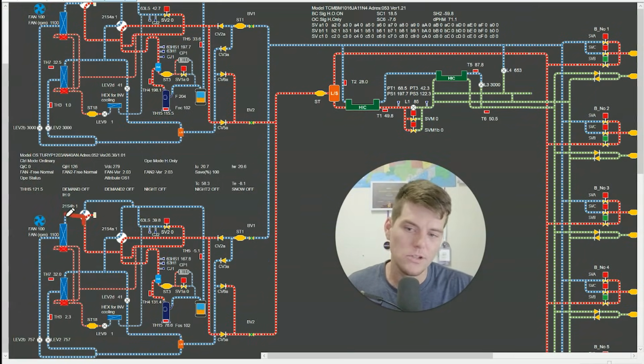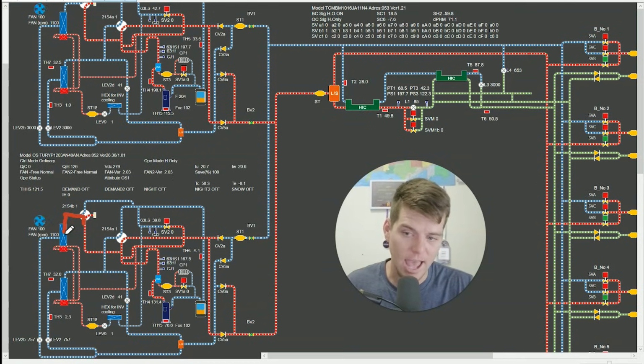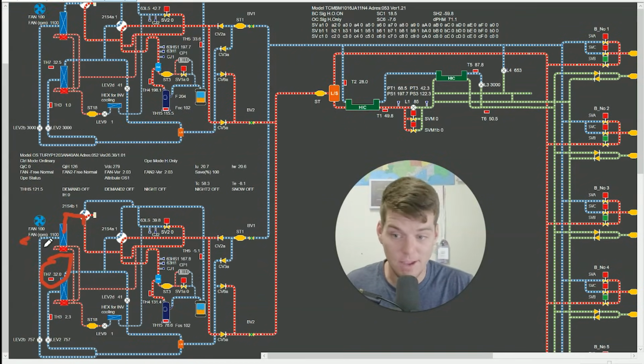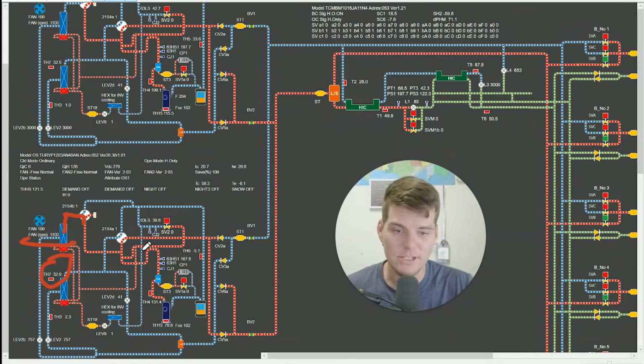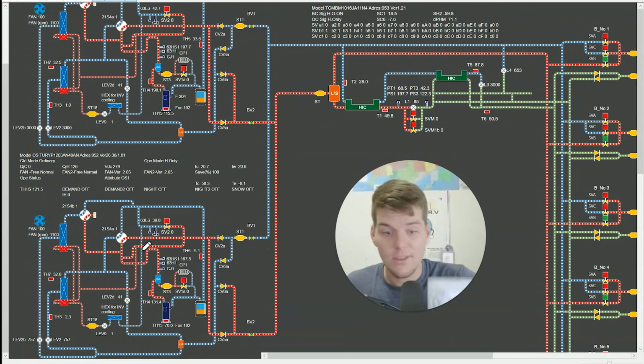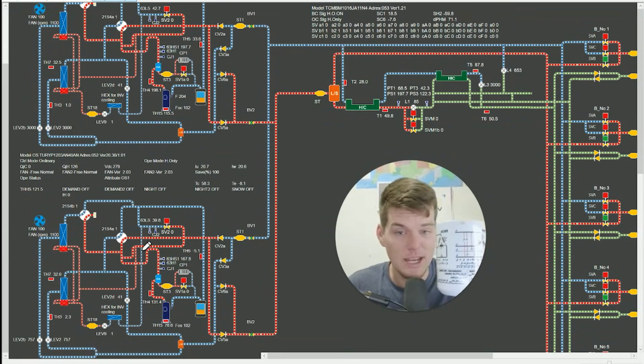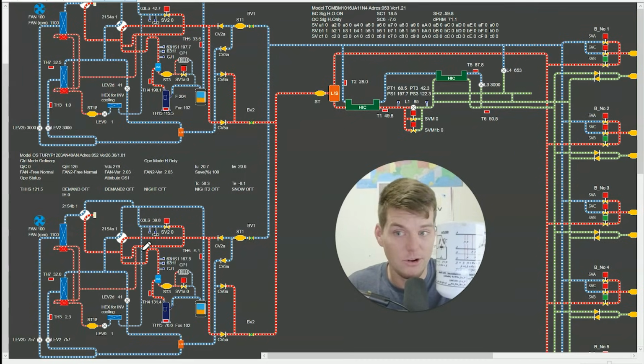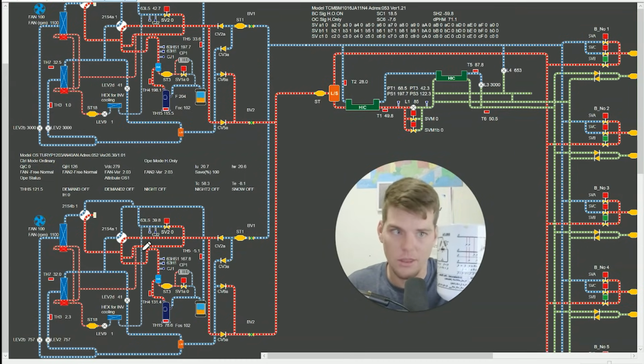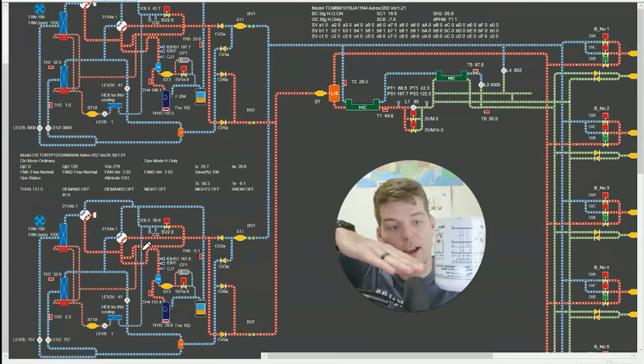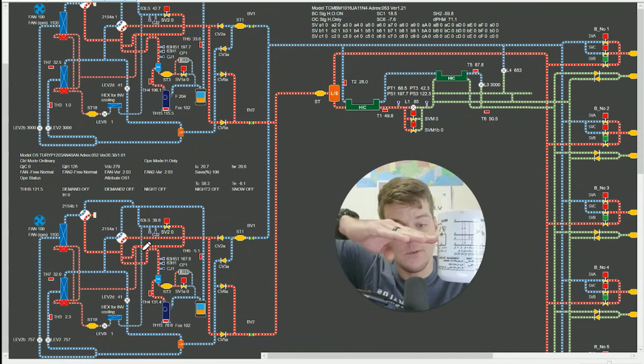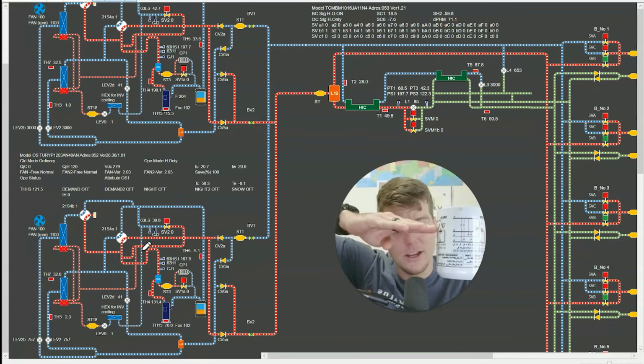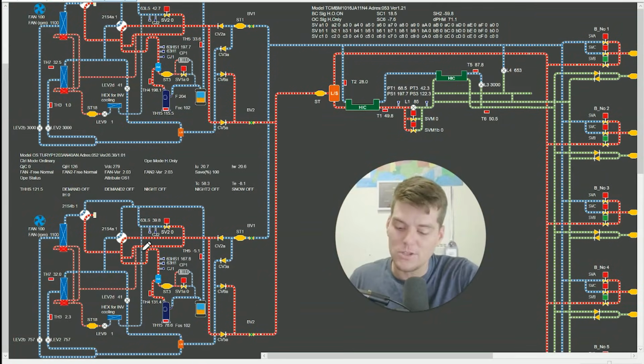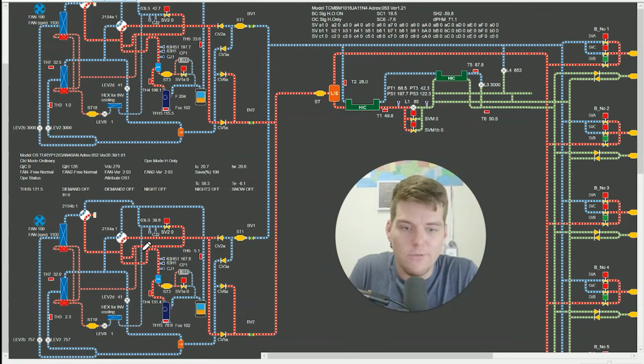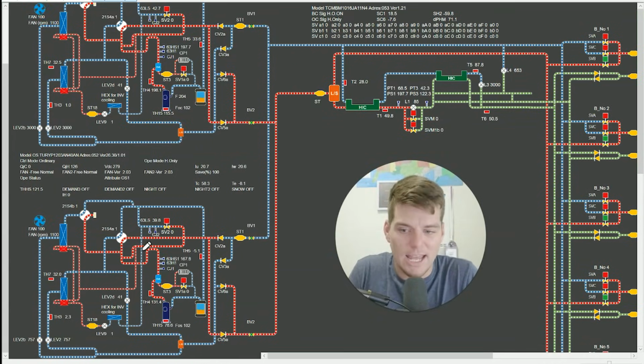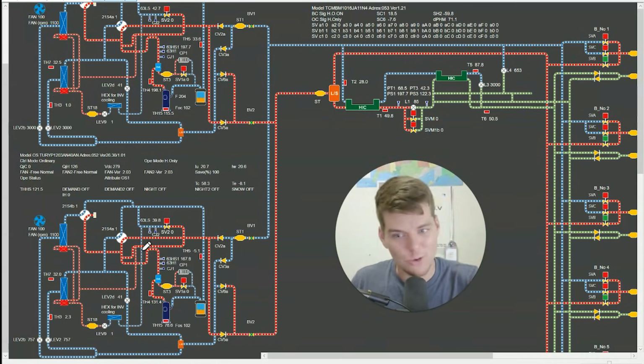So what happens here? Well, when this turns over and it floods this with hot gas at 32 degrees outside with the fan at full tilt, it turns into a liquid receiver. Well, what do you mean? Well, I mean that if this coffee cup here is your outdoor heat exchanger and you send hot gas to it at a 32-degree ambient and I'm blowing a giant fan across it, again, it's basically in a freezer, it's going to turn all that hot gas into what? It's going to turn it into liquid. And what's going to happen? It's going to slowly fill up the outdoor heat exchanger full of liquid. Well, what happens when you take an outdoor heat exchanger and you fill it full of liquid? Well, now it's just a giant 410A tank attached to the unit on the outdoor section.